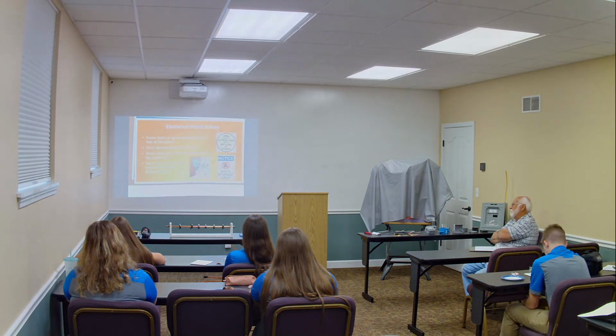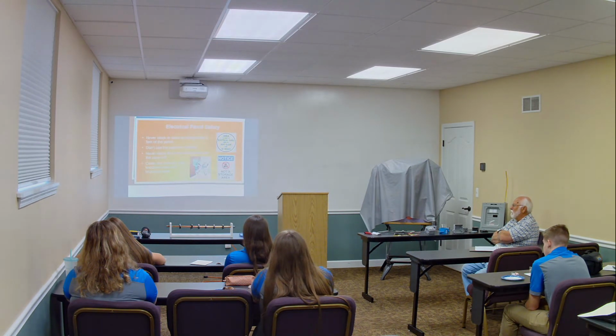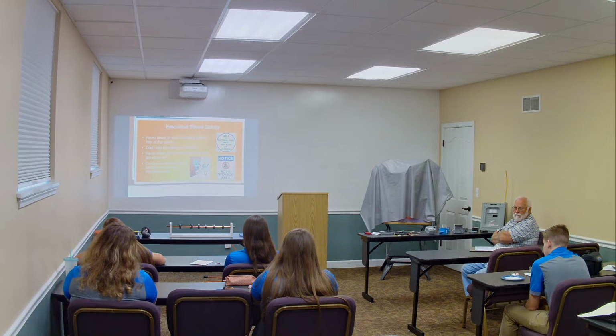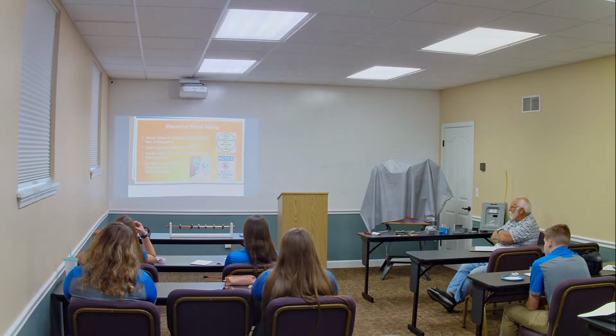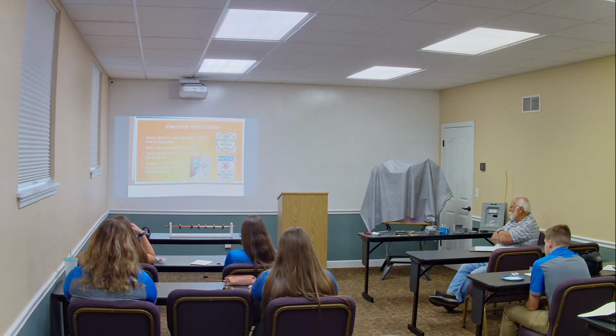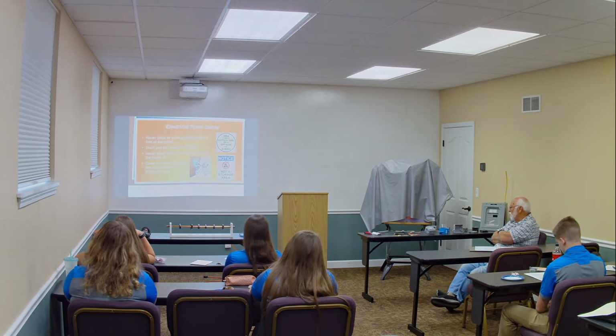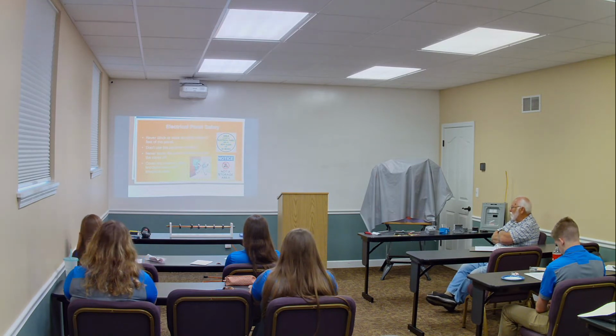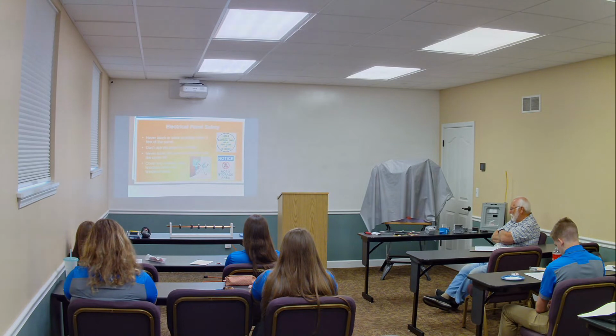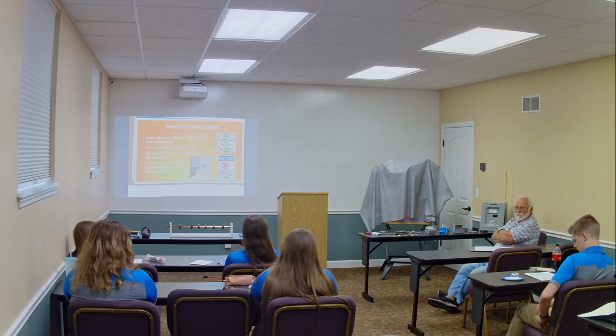So you never block or store anything. Actually, it's the law within 3 feet of a panel. You're never supposed to use the panel for storage. So you see electrical panels open and there's screwdrivers in there, or a bottle of water or something. It's not a storage cabinet. You don't ever leave that panel unattended with the cover off. But there again, you guys should never have a cover off a panel because it's dangerous. And you cover any of those. We showed the knockouts on that little panel where the breaker shows through. You never have any open slots there. If you do, there's special seals that go over there, because otherwise that thing is open and you could put something in there.